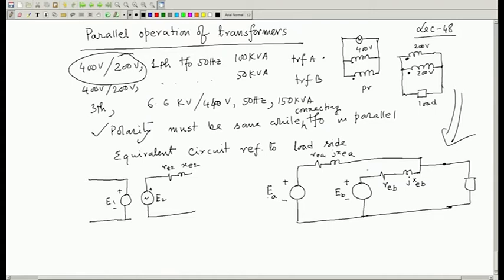Now, in general, if the voltage ratings are the same, and you apply 400 volt here, this induced voltage will be 200 volt. So, here also it will be 200, here also it will be 200 volt, and you get the current. Now, at this point I will tell you that after all, these two are different transformers. So sometimes, when you have applied the same primary voltages to the primaries of these two transformers, there may be a slight difference in the secondary voltages. For example, this is 200 volt, this may be 208 volts. They are not after all identical, there may always be a slight difference.